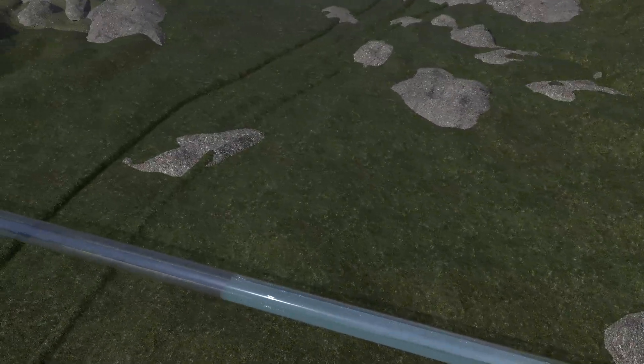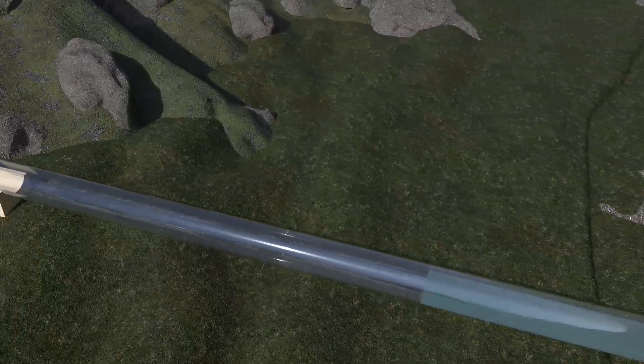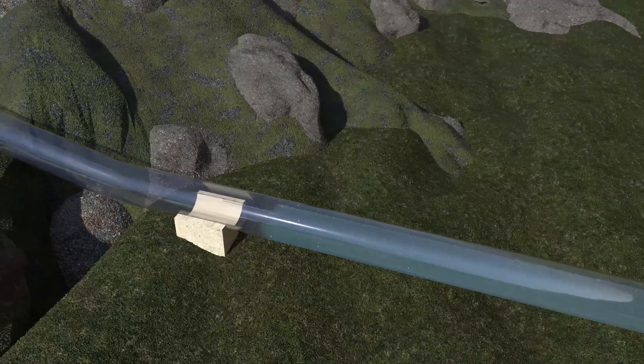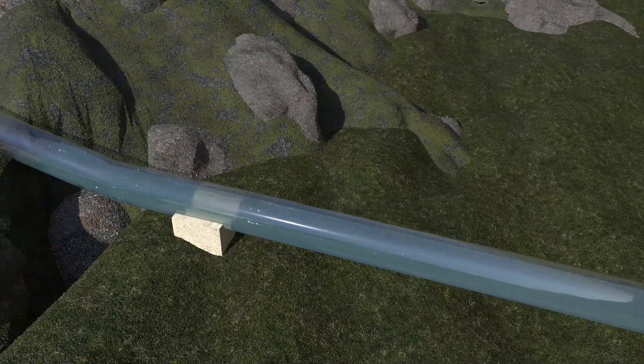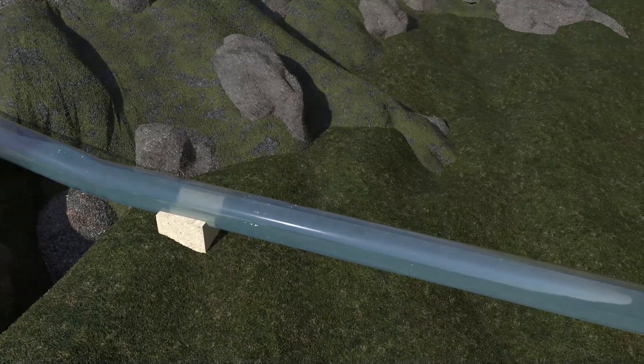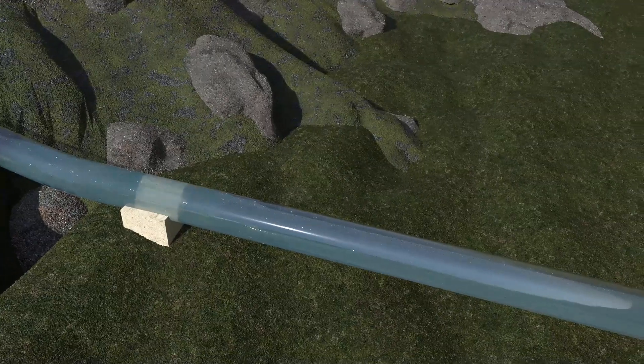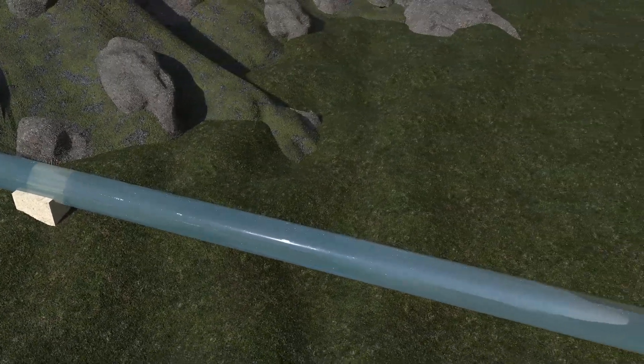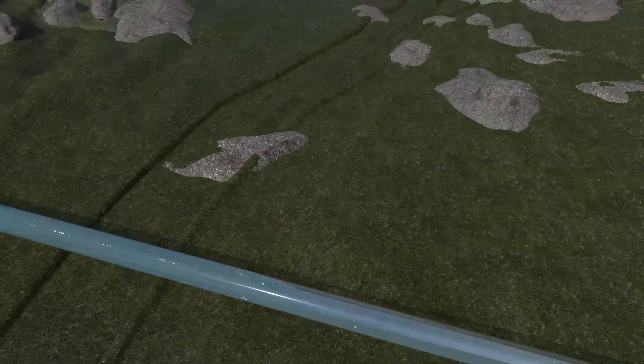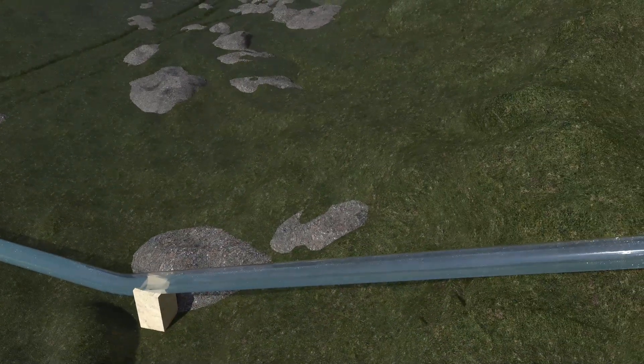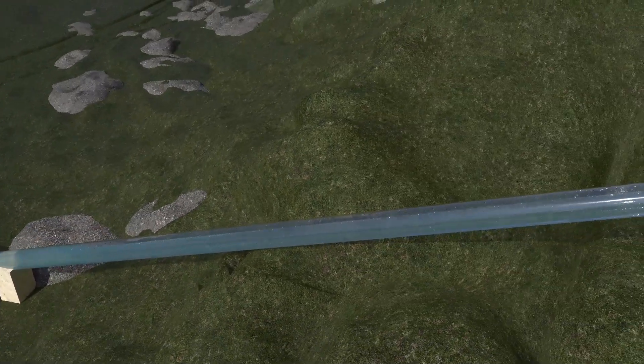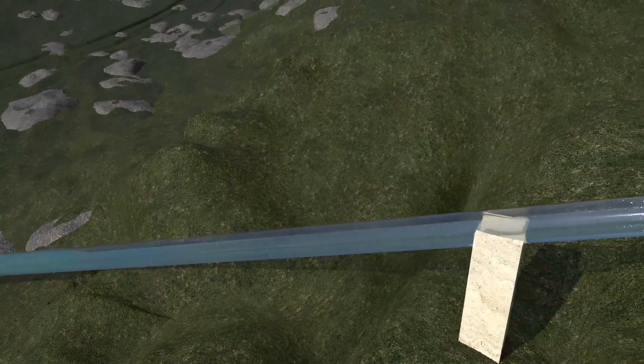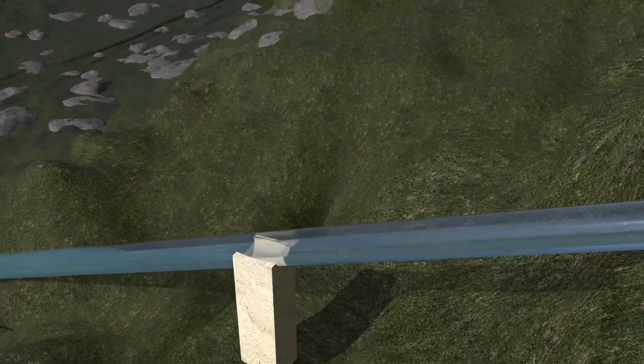As the air moves along, we reach a certain point where before progressing further, the remaining part of the segment upstream must be pressurized, locating the air pocket on the high point itself, protruding downstream. The same is repeated in the same manner for the rest of the high points.